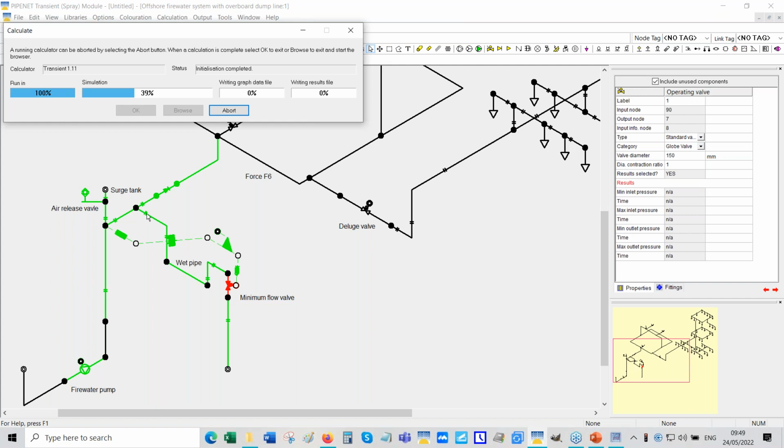That these pipes will get flooded. When they get flooded, this column of water will get pushed out through the system. It'll be like a slug that flows down the line. And that is what we're trying to model. Okay, and of course there's this control system on the overboard dump line as well. What is of most interest is what happens to the slug of water.